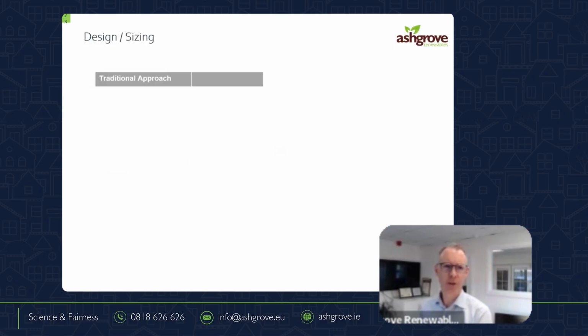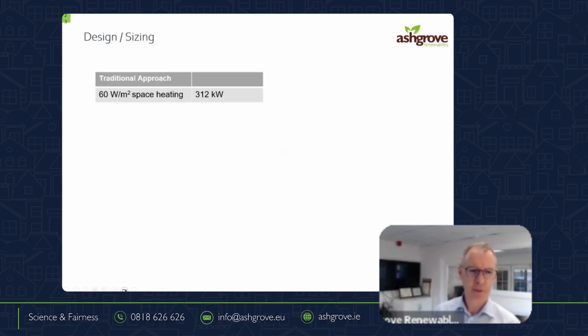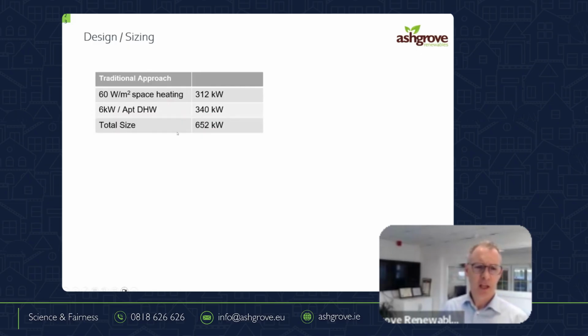I'm going to jump into the one we just looked at. And here was the thinking. The engineers had actually, believe it or not, done the same heat loss calculations as we had, but they weren't quite confident with them. So they put in 60 watts per square meter, a bit of breathing space, a bit of safety. But when I multiplied it out by the entirety of the building, it came to 312 kilowatt, and they were allowing 6 kilowatts for hot water per apartment, right? And that gives another 340. And then the total size was 652. If we used the information that we had gathered from Denmark and these places, like Denmark has 68% district heating, so they know not everybody will use hot water simultaneously, and they have all of these calculations for doing that.